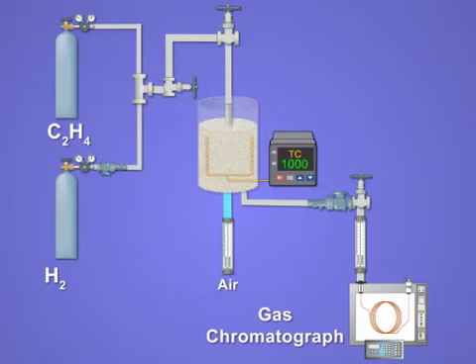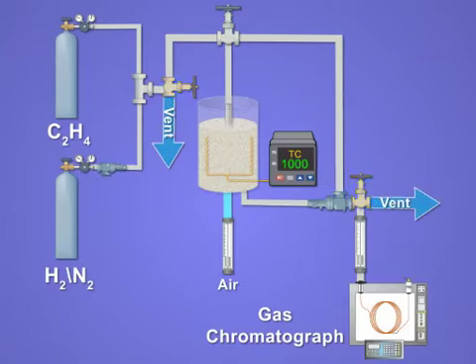Flow rates are monitored using bubble meters and rotameters. For safety, diluted reactants, high-pressure relief valves, high-temperature shutdown, bypass and venting systems, and a combustible gas leak detector are installed.